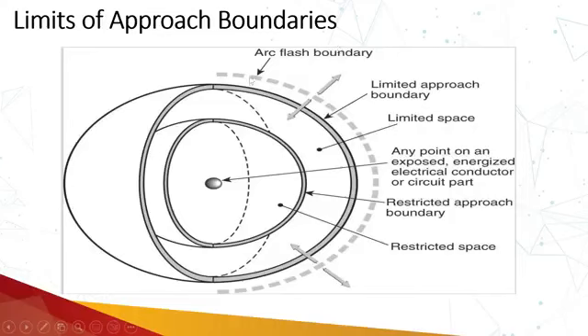And what is this arc flash boundary? It is basically the boundary at which there is a chance of a second degree burn, when the incident energy is around 1.2 cal per centimeter square. You see that they have mentioned this arc flash boundary outside as well as inside as well. So what does this mean?